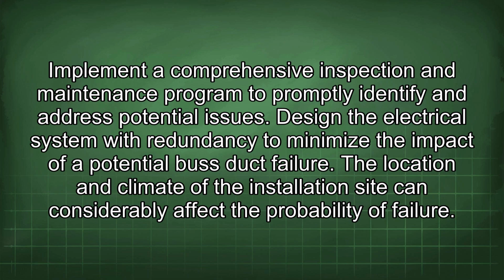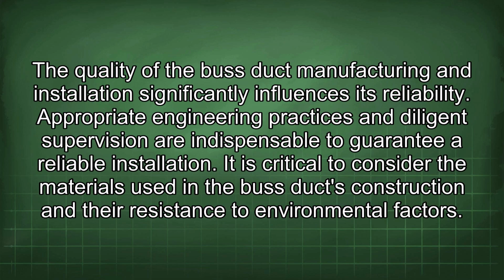The location and climate of the installation site can considerably affect the probability of failure. The quality of the bus duct manufacturing and installation significantly influences its reliability. Appropriate engineering practices and diligent supervision are indispensable to guarantee a reliable installation. It is critical to consider the materials used in the bus duct's construction and their resistance to environmental factors.